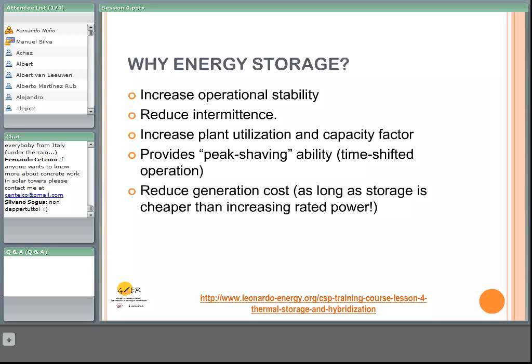For example, the case in Spain, where we have a solar thermal power plant, the Gemasolar power plant. We'll talk about it later, which is just 17 megawatts in rated power, but it provides storage for 15 equivalent hours. So the generation of this plant with only 17 megawatts rated power is similar to the generation of a 50 megawatt plant during the year.